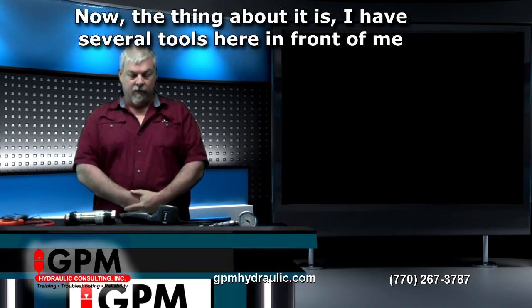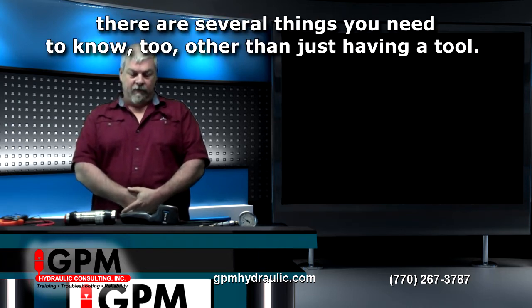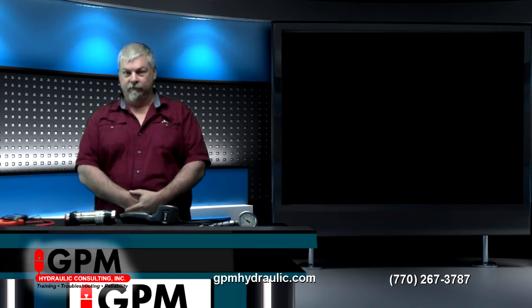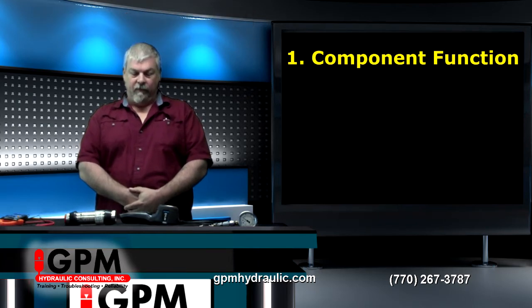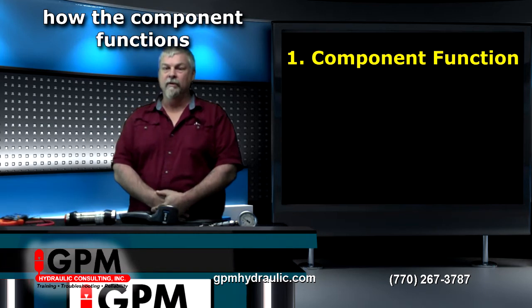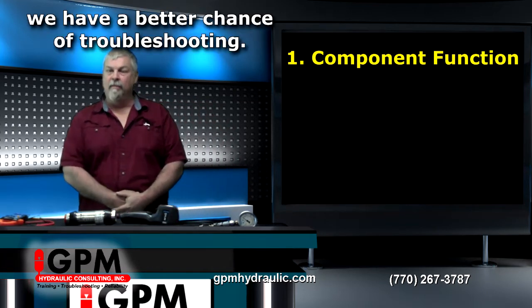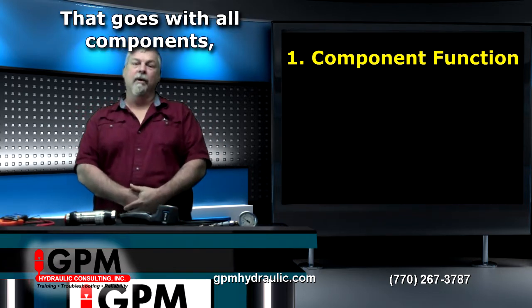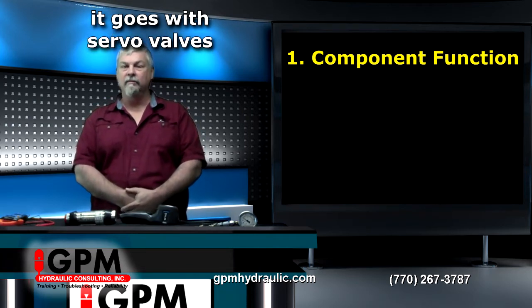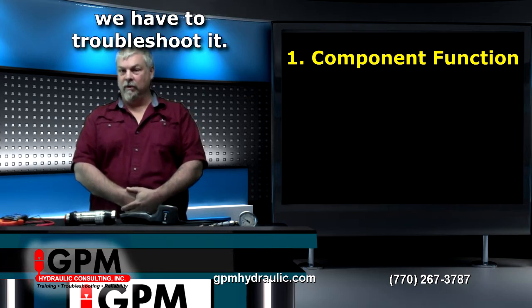There are several tools here in front of me that you can use, but there are several things you need to know other than just having a tool. The first is component function. It's very important that we know how the component functions. If we understand how the pump works, for example, we have a better chance of troubleshooting. That goes with all components — relief valves, servo valves, and cylinders. The more we know, the better chance we have to troubleshoot.